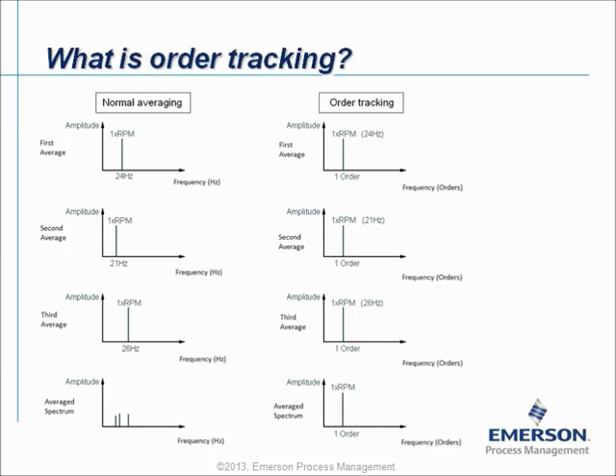To overcome that, if you also have a speed pulse — a tach pulse — you can do order tracking. During data collection, the horizontal axis units are converted into orders. So the 24 Hz is expressed as one order, the 21 Hz is expressed as one order, and the 26 Hz is expressed as one order. If you now do averaging based on order, you have a spectrum stored that is meaningful. We will now take a look at how to do that on the CSI 2140 Machinery Health Analyzer.